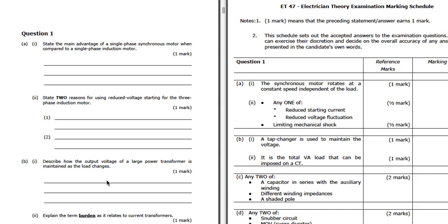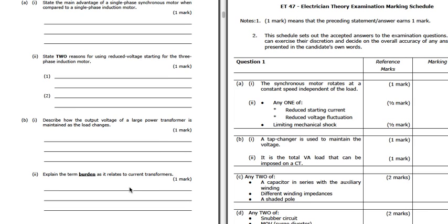Describe how the output voltage of a large transformer is maintained as the load changes. So as we know, as we load up a transformer, because of the impedance of the transformer and the current flowing through the impedance, we'll get a volt drop. And so what we need to do is we need to have a tap changer to maintain the voltage. So we tap off at a different point of the secondary winding to increase the voltage. The term burden in the current transformer, that's the total VA that can be imposed on the CT. So it's the total load that it can take.